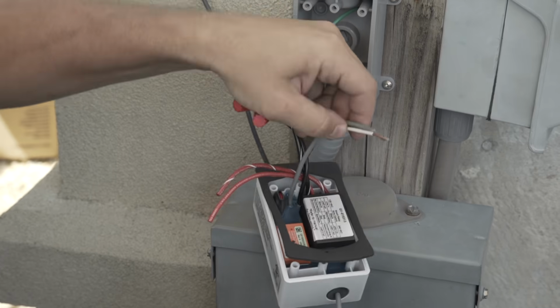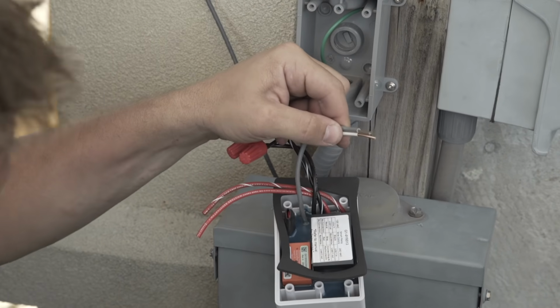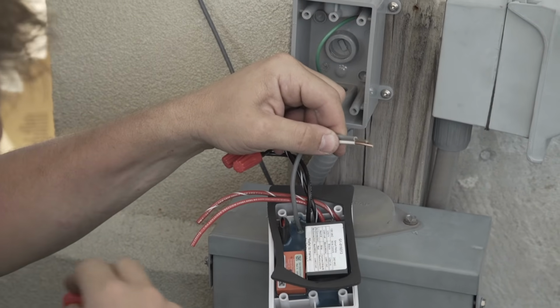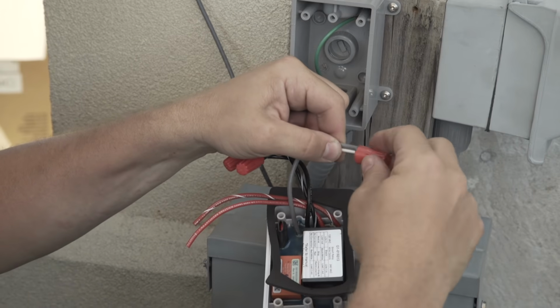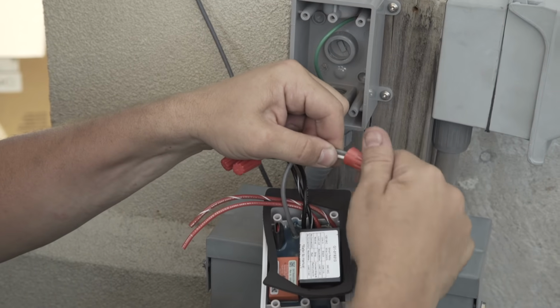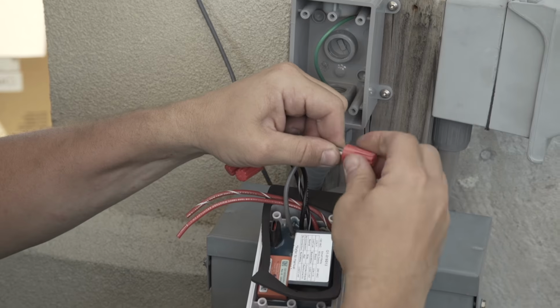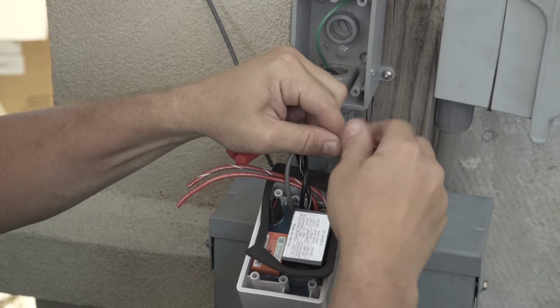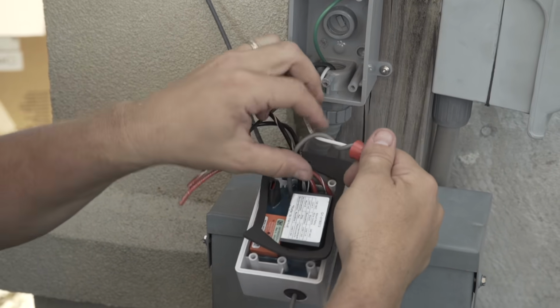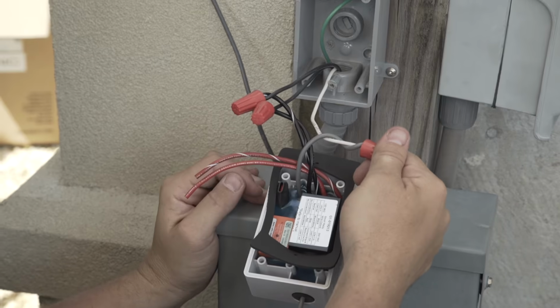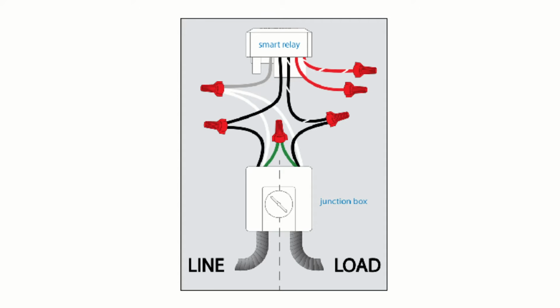The next step is to mount the smart relay into an existing single gang box or install the Hayward supplied single gang box, depending on the application. Since we are using the smart relay for a light, it will be wired with 115 volts. Please refer to the owner's manual and quick start guide if this relay is being used for another piece of equipment requiring 240 volts. Shown are the wires coming into the smart relay from the power source or power line, then going out to the light or load.